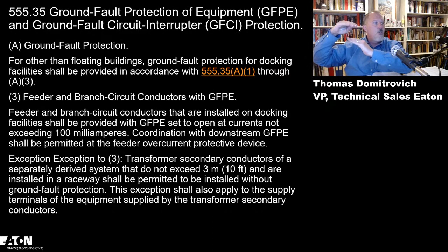Why? What do they mean by that? Well, let's talk about, if you had an overcurrent protective device, a standard, not a thermomagnetic breaker, say a circuit breaker with an electronic trip unit. That's sort of what the trip curve would look like. We call that the time current characteristic curve, where we have current across the bottom and time up the side, right? For increased amounts of current, we have a decreased amount of clearing time. This tells you how long it will take that breaker to trip based upon various values of current.